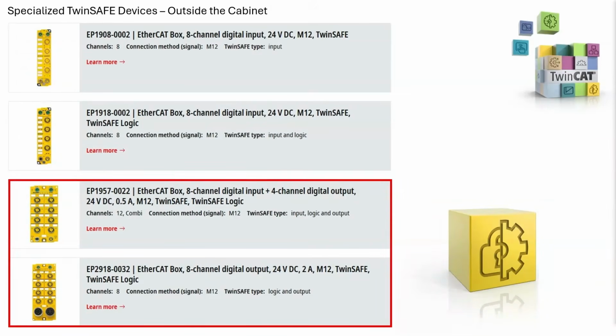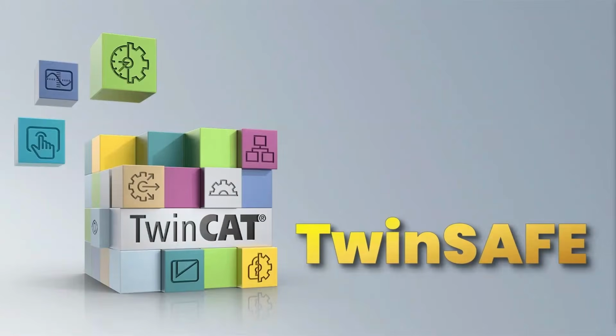Both the EP1957 and EP2918 extend TwinSAFE functionality into the field with safe outputs and distributed safety control. The EP1957 combination module provides 8 safe inputs and 4 safe outputs, all housed in a rugged IP67 enclosure with M12 connectors for reliable operation in harsh environments. The EP2918 provides 8 safe output channels for directly switching actuators such as contactors, valves, and safety-rated devices, up to 2 amp compared with half amp on the EP1957. Both modules offer integrated TwinSAFE logic functions, thus allowing us to implement modular distributed safety architectures without relying on cabinet-mounted hardware. That wraps up the hardware overview for part 1.